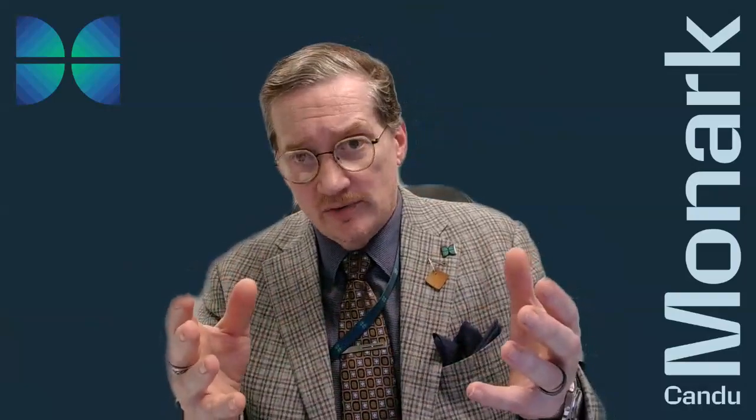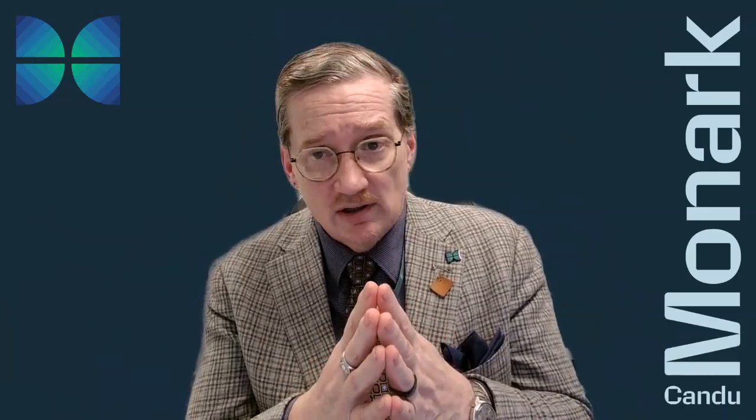So let's talk about containment. One of the things that's come up, we have unitized single unit containment, whereas all of the Ontario reactors have a multi-unit containment concept with a vacuum building, right? Now, a lot of people dunk on that concept in general. It's certainly true that it's unique to Canada, but in my opinion, I don't think there's anything wrong with it. It has weaknesses because you've got safety systems that are interlinked across multiple units. Outages and maintenance and things like that can be very problematic and hard to manage. But we've worked out ways to do it over the decades, right? But that whole negative pressure containment approach is really very interesting and novel, and it brings benefits as well.